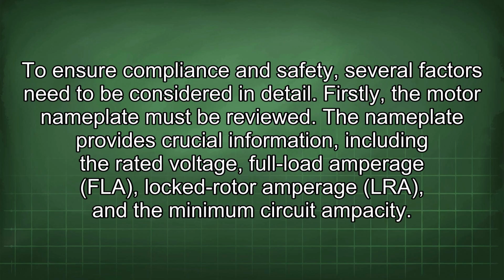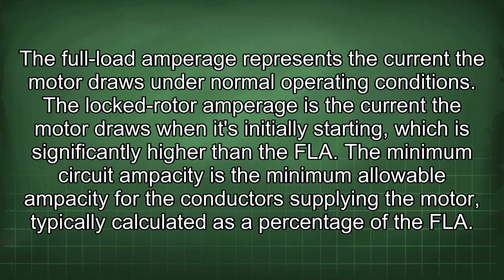Firstly, the motor nameplate must be reviewed. The nameplate provides crucial information, including the rated voltage, full load amperage (FLA), locked rotor amperage (LRA), and the minimum circuit ampacity. The full load amperage represents the current the motor draws under normal operating conditions. The locked rotor amperage is the current the motor draws when it's initially starting, which is significantly higher than the FLA.